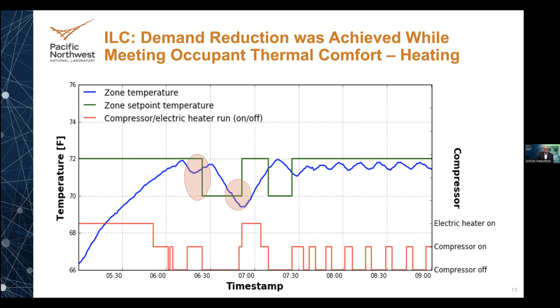The demand reductions that I showed in the 2 previous slides were achieved while maintaining comfort. Zone temperature is on the left y-axis, and zone set point in green is also on the left y-axis. And then the compressor on-off status is on the right side. So the normal set point for heat pump 8 is 72 degrees F during heating season, while we reduce this to 70 when we want to manage the load. So that's what you see in here. You can also see that the blue line typically is between 70 and 72 degrees, which is what is established as a comfort requirement for this particular zone. Each zone can be customized to whatever requirements for that zone.